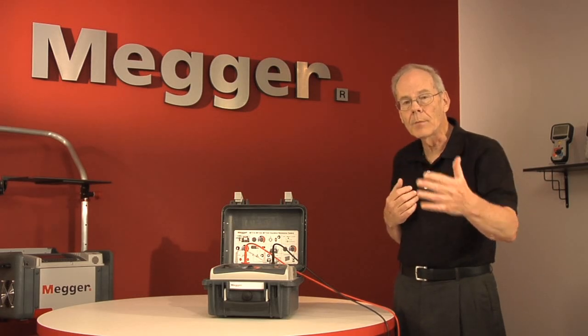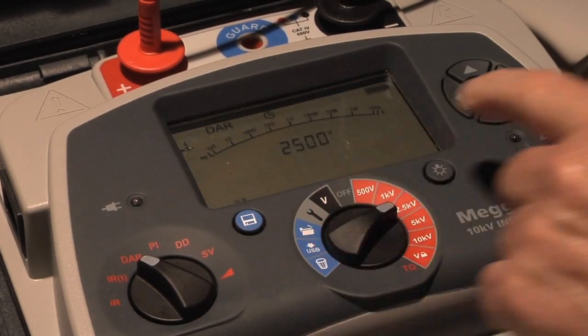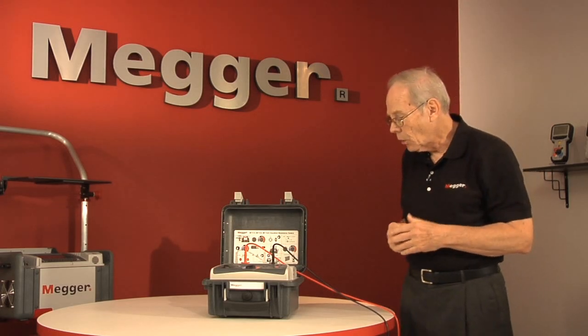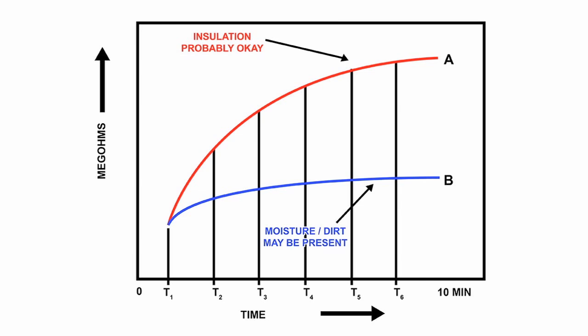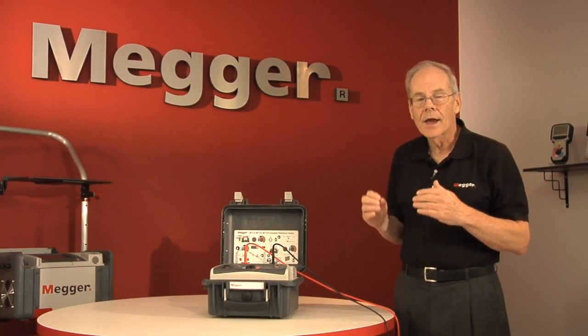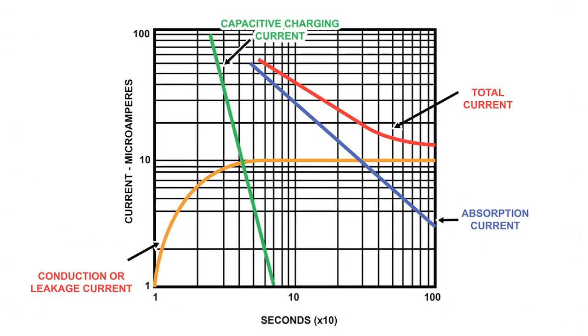The tester will automatically run the test for that time. At the end of the test, all the data is shown on the display — it will show you time one, time two, and it will calculate the ratio for you. The goal is to look for a relatively high ratio, because insulation that has deteriorated will show relatively little charging effect but a lot of leakage effect.